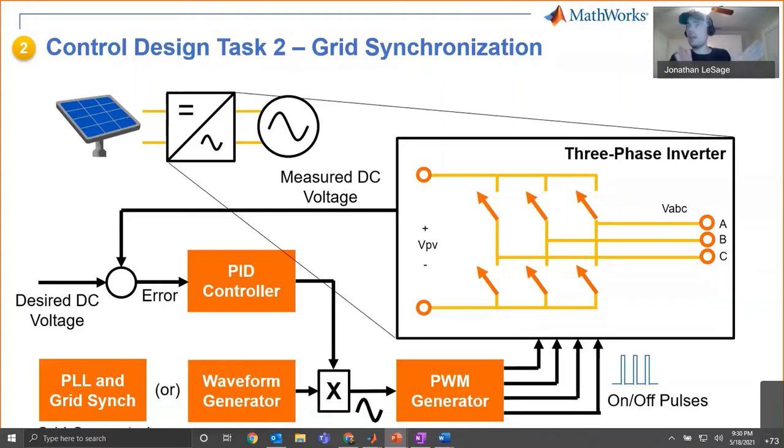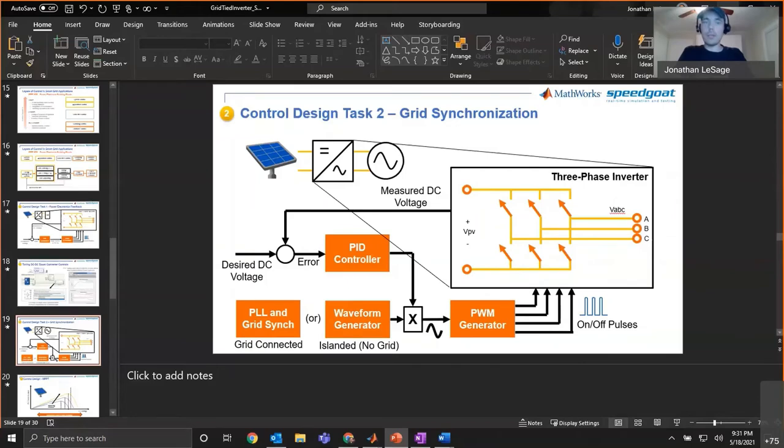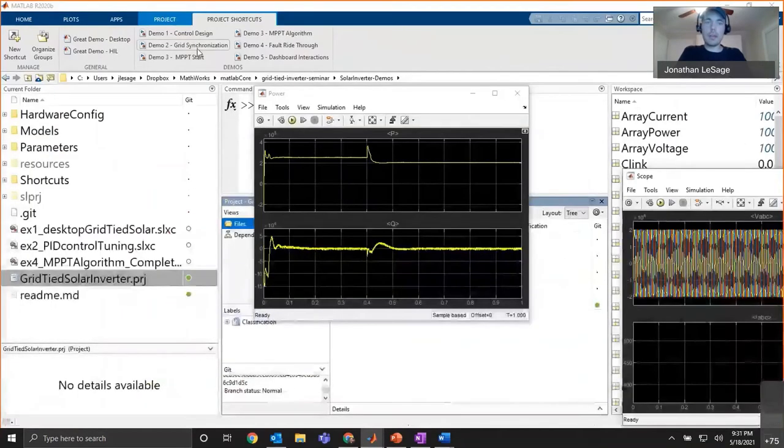If we don't do that, and then we try to connect our solar generation plant to the grid, we're going to have extremely large control transients and potential arcing on the actual breaker system. And so, again, that's something that you don't want to happen in reality, right? In simulation, of course, it may just give you very crazy voltage transients, but in reality, that's going to cause serious damage to the equipment, okay? And so the way that we can do that, just real quick, example here.